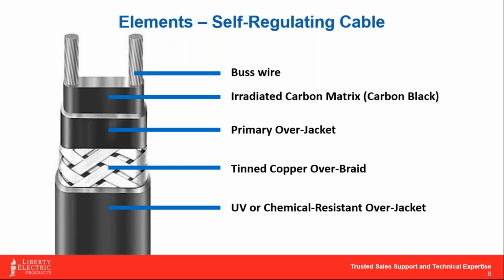I point out that primary over jacket because when a cable is rated at 50 degrees F, it's not going to go much below its rated duty, since the jacket doesn't allow the cable to physically expand out further the way it would like to. For example, with a 5 watt per foot cable, the lowest output you might get out of it is about 3.5 to 4 watts per foot, because that primary over jacket won't allow it to expand any further.